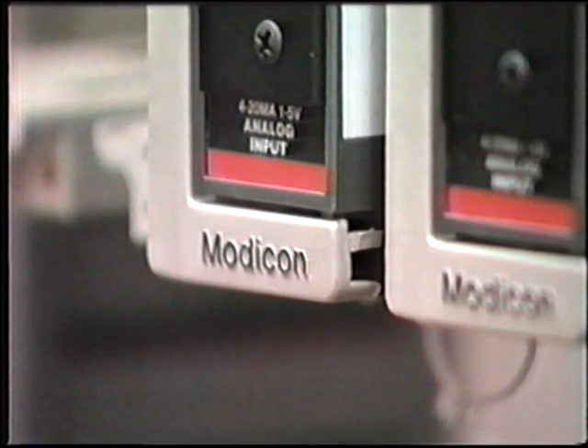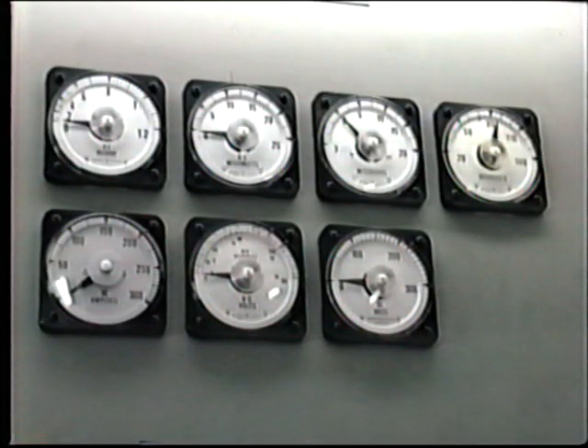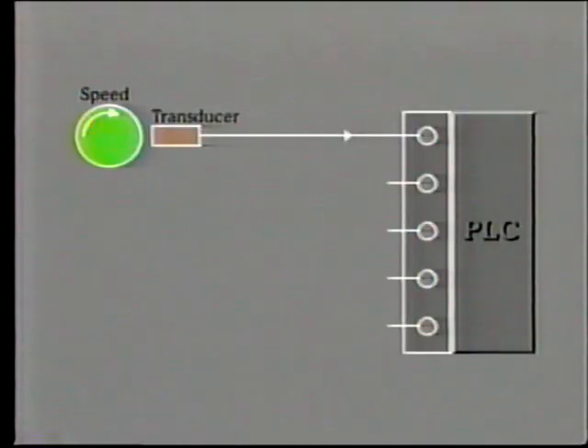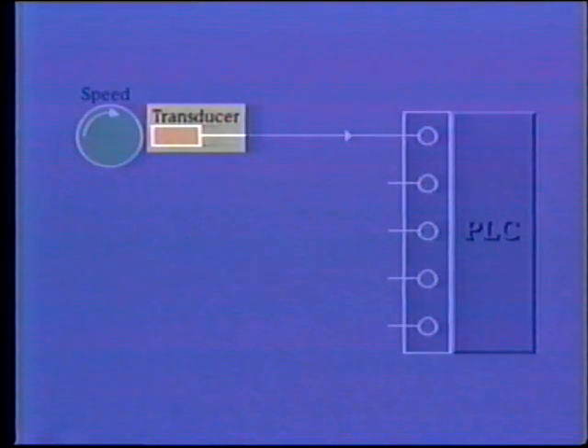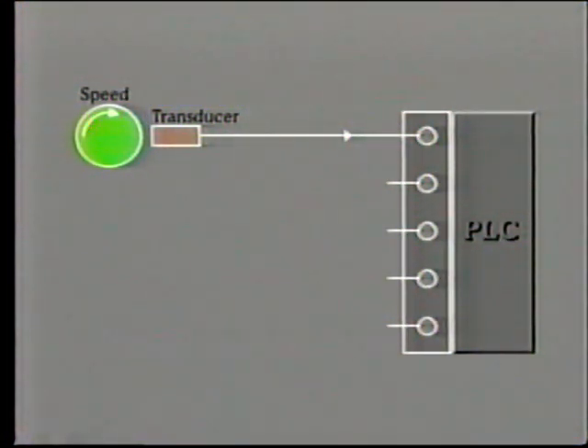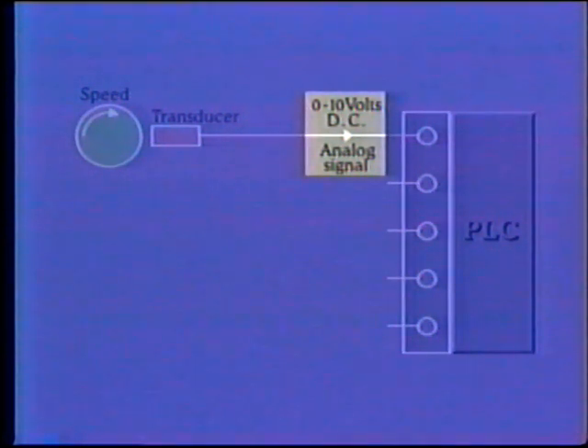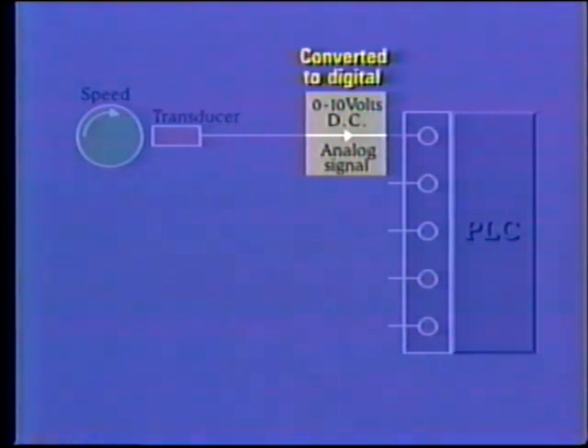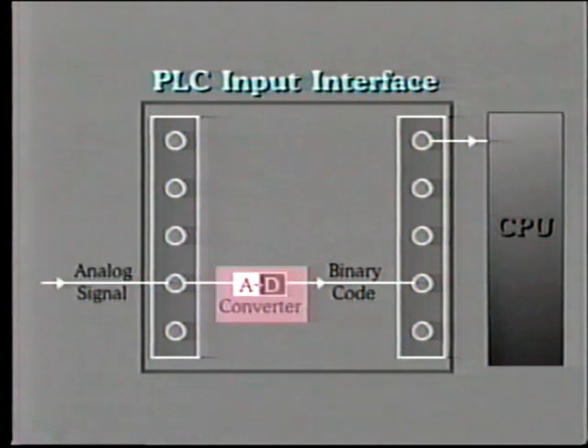But incoming signals are not always discrete on-off signals. In some cases, we may need to input analog signals. For example, voltage, current, speed, a position indicator, in fact, any required measurement of a continuously varying quantity. For many analog signals, the voltage source is obtained at the sensor, usually from a transducer which typically provides a 0 to 10 volt DC signal. Before the analog signal can be used in the CPU, it must be converted to a binary code digital signal. For each incoming analog signal, the input module must provide analog to digital conversion. The output from the A to D converter is in binary form, representing the input value at any specific time.